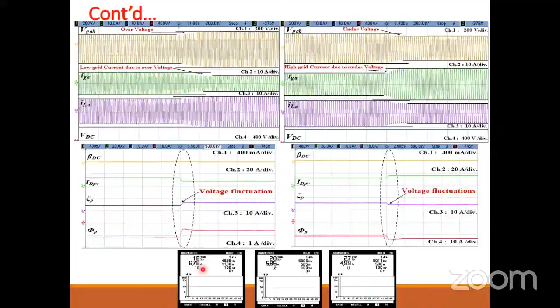What is THD? Simply, all the harmonic components divided by the fundamental component, multiplied by 100. Or you can say the percentage of all harmonic components with respect to the fundamental is your THD, right? So here the denominator is your fundamental component. During this over voltage condition, the denominator is decreasing. If your denominator decreases, then definitely the ratio will increase. And in this situation, if the denominator is increasing, automatically the ratio will decrease. So that's why this happens. It does not mean that your harmonics are increasing, but because the denominator component is changing accordingly, the percentage harmonic number is changing. Okay. This is the situation.